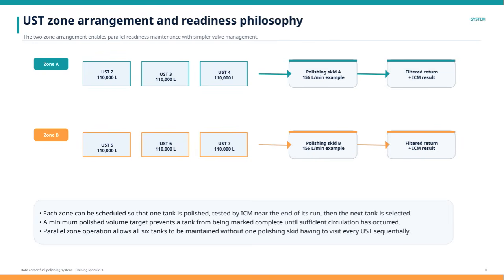Additionally, a minimum polished volume target is set. This means a tank isn't considered fully serviced until enough fuel has circulated through the polishing skid, ensuring thorough cleaning. By running both zones in parallel, the system efficiently maintains all 6 tanks without requiring a single polishing skid to service every tank one after another. This approach increases operational flexibility and reduces downtime, ensuring that fuel quality and readiness are consistently upheld.